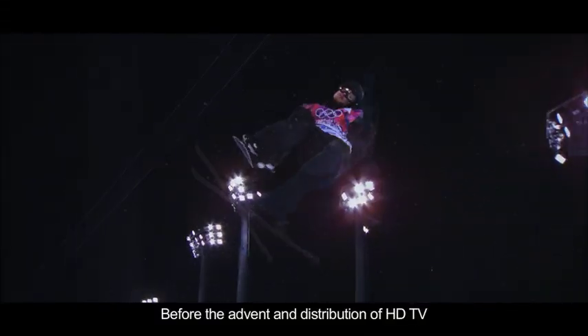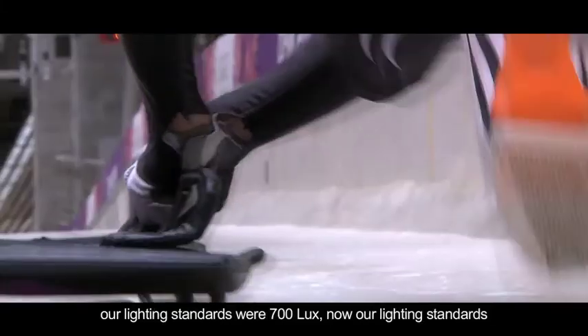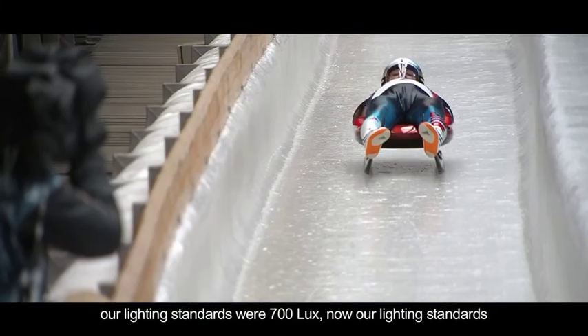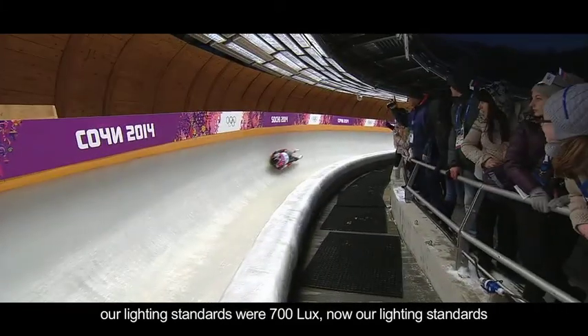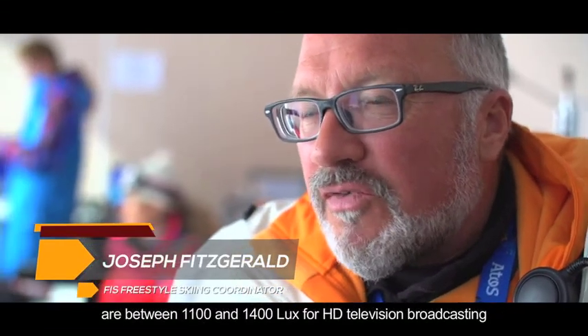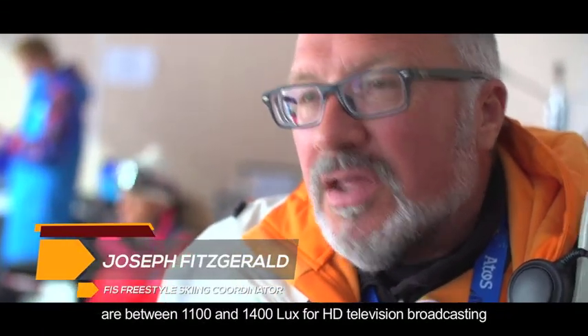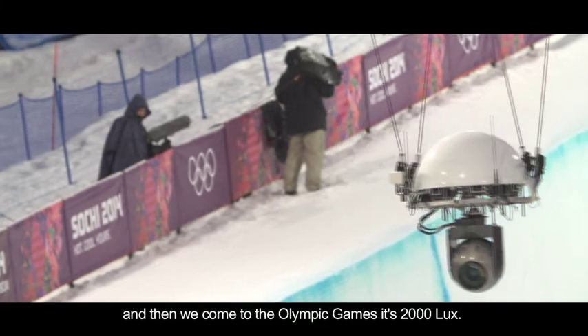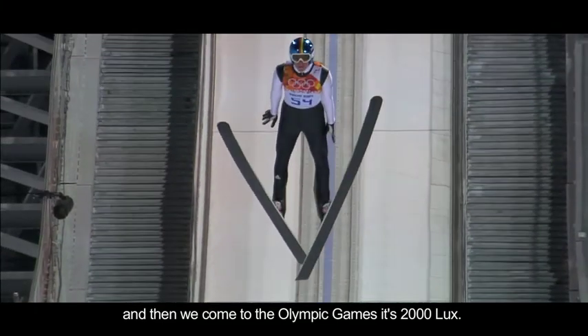Before the advent and distribution of HD TV, our lighting standards were 700 lux. Now our lighting standards are between 1100 and 1400 lux for HD television broadcasting. And then we come to the Olympic Games, it's 2000 lux.